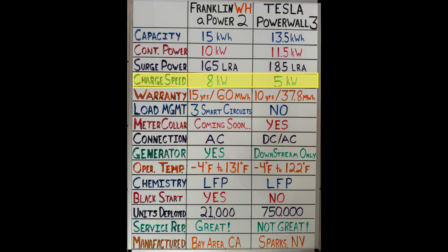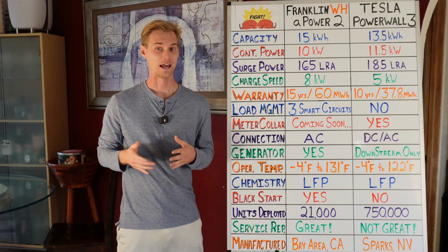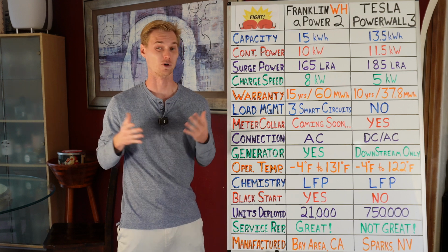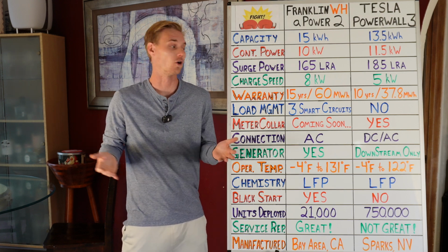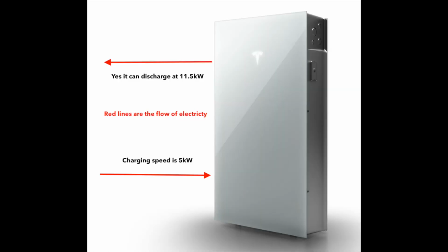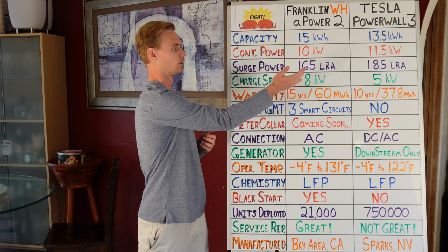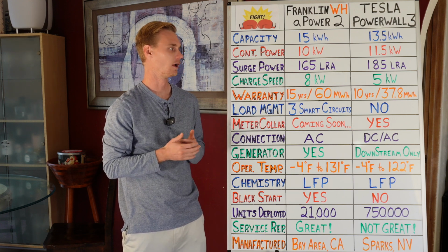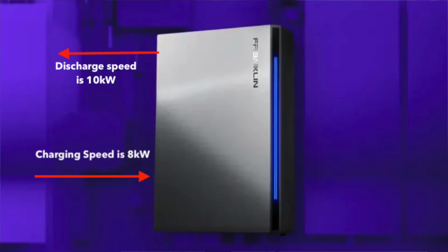Now, charge speed. This is something even Tesla and the rep we work with kind of played dumb about for a long time, because I don't think they really wanted us to know. Everyone talks about how with the Powerwall 3 you can discharge at 11.5 kilowatts. Amazing. But when you're charging the battery, when power is going the other way, it can only absorb about 5 kilowatt hours per hour at that rate. This is where the Franklin can really benefit you if you're trying to get away with just one battery and want to make sure it actually charges fully.